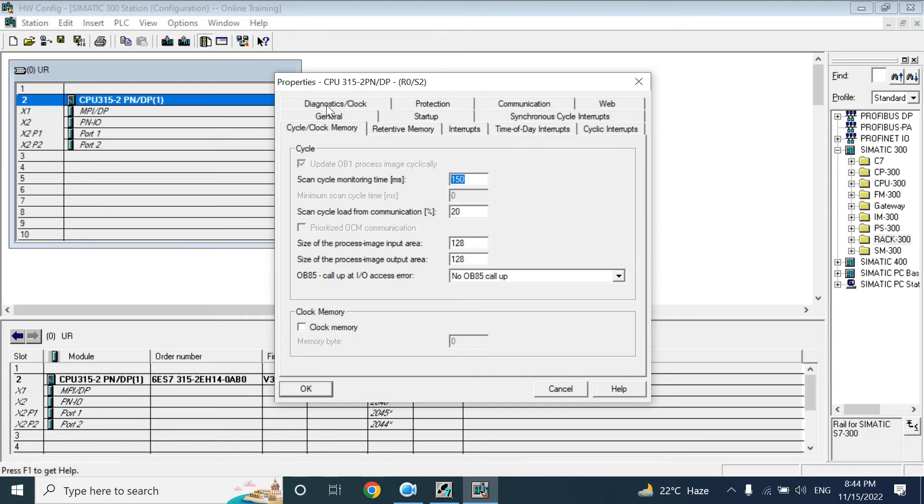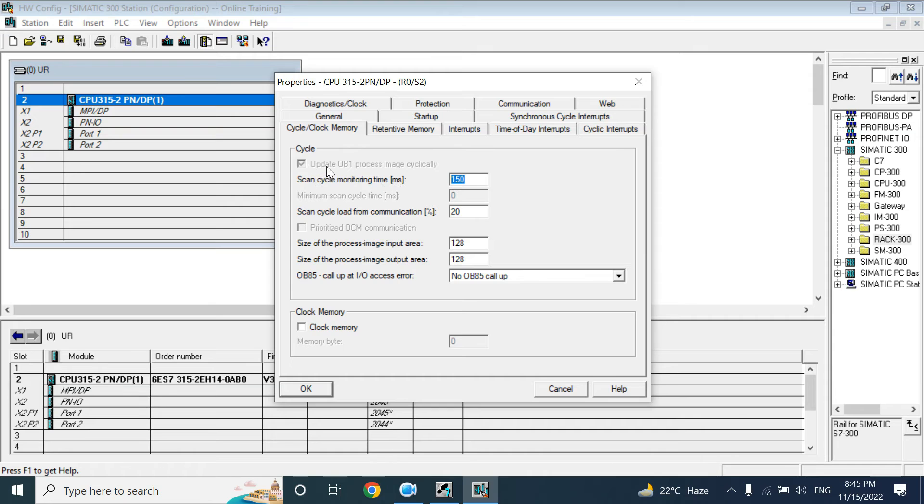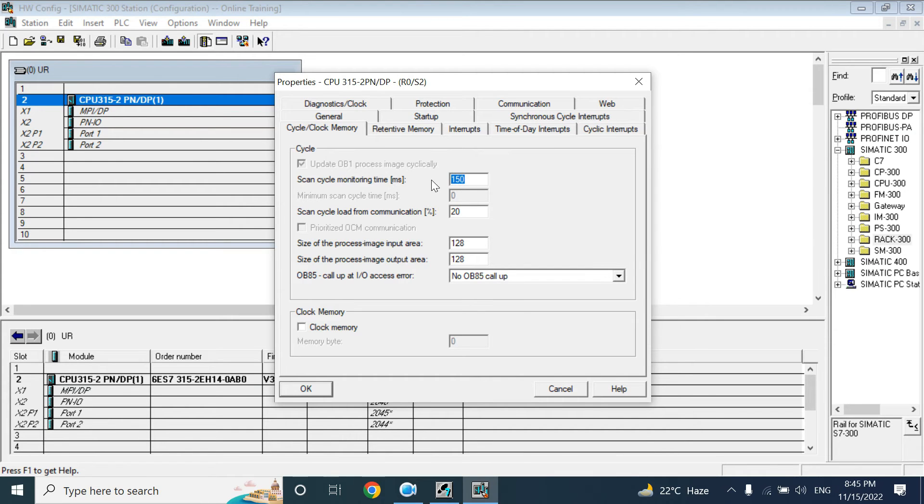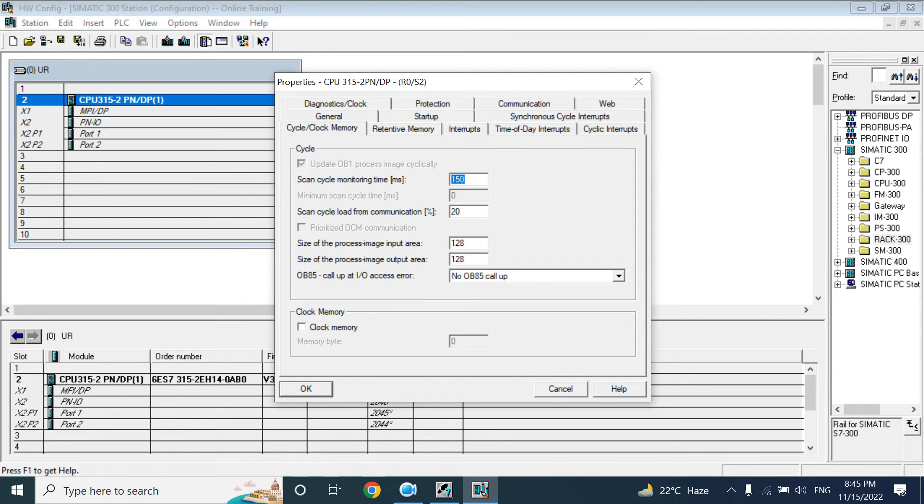Here is the Cycle and Clock Memory. Here you can see the scan cycle monitoring time showing as 150 milliseconds. That means the OB1 update cycle process cycle. If your program, your user program, takes more time, more than 150, your CPU will go to stop mode. But this is the maximum cycle time that will be allowed. Normally it will take 1 to 10 milliseconds. But if your program is large, then it will take more time to scan the full program.